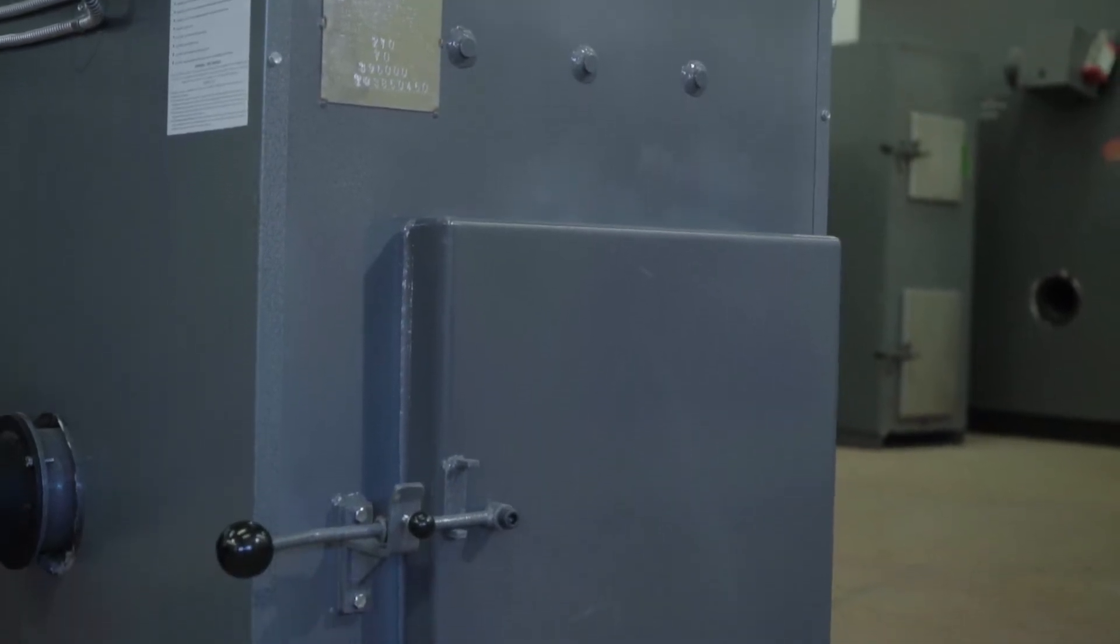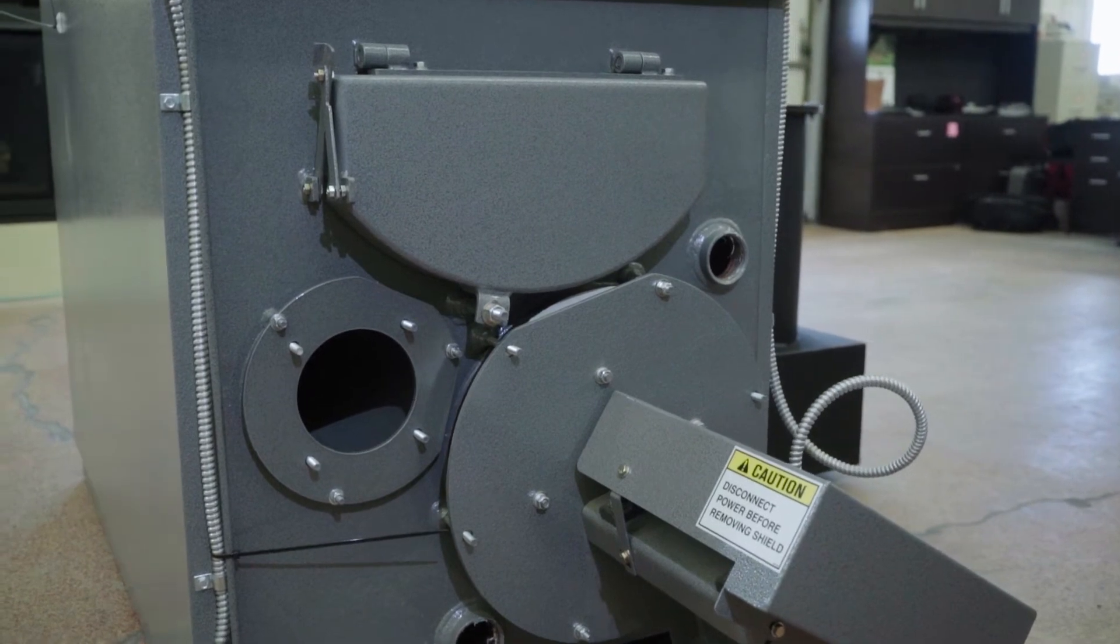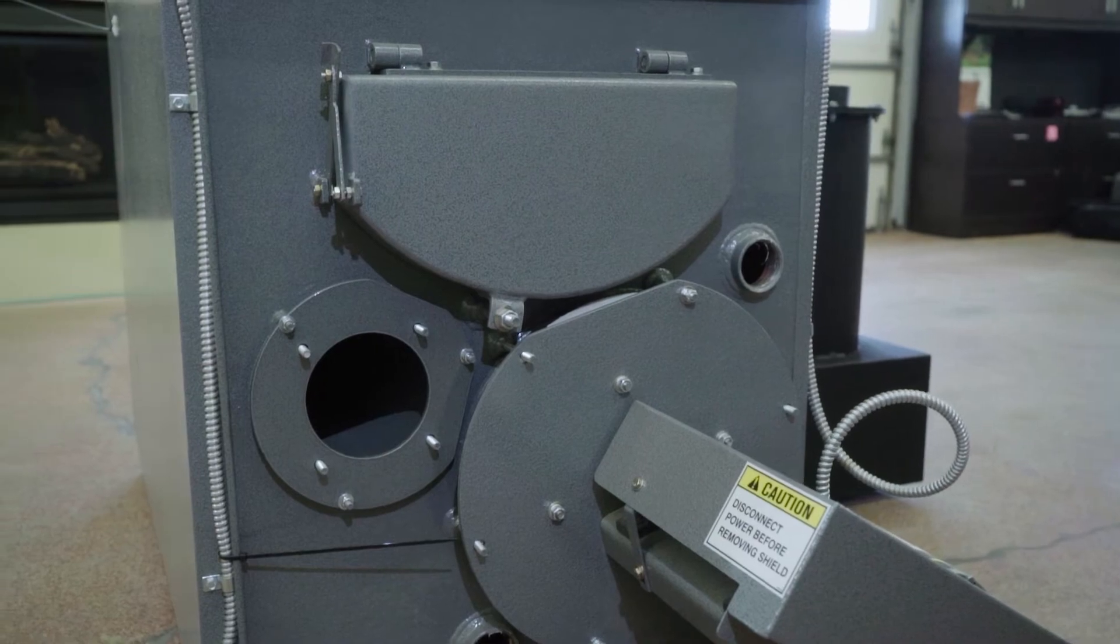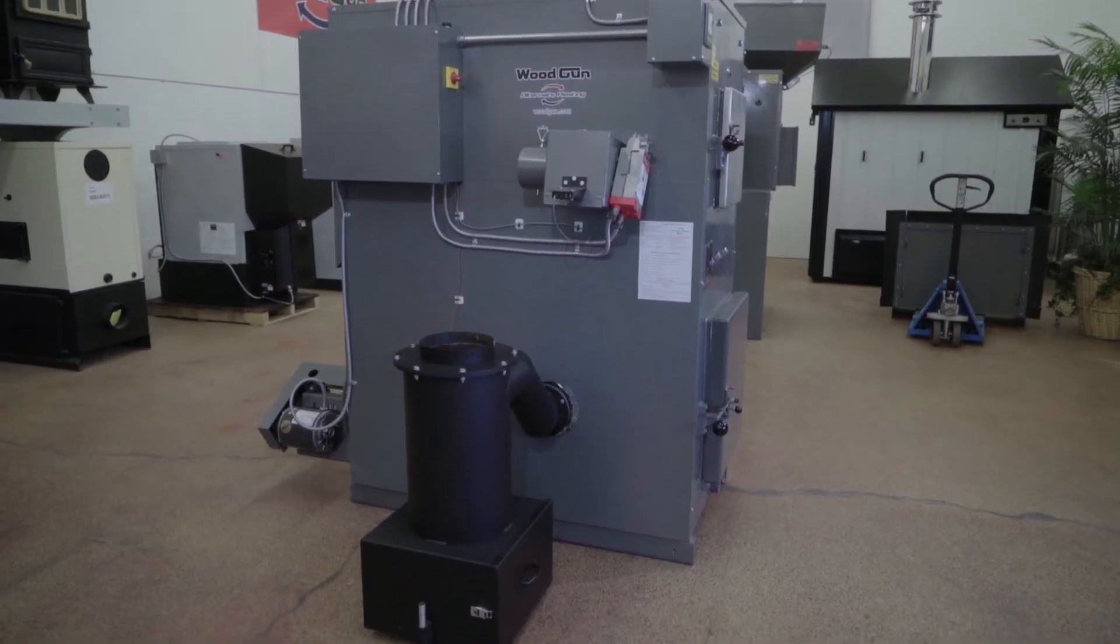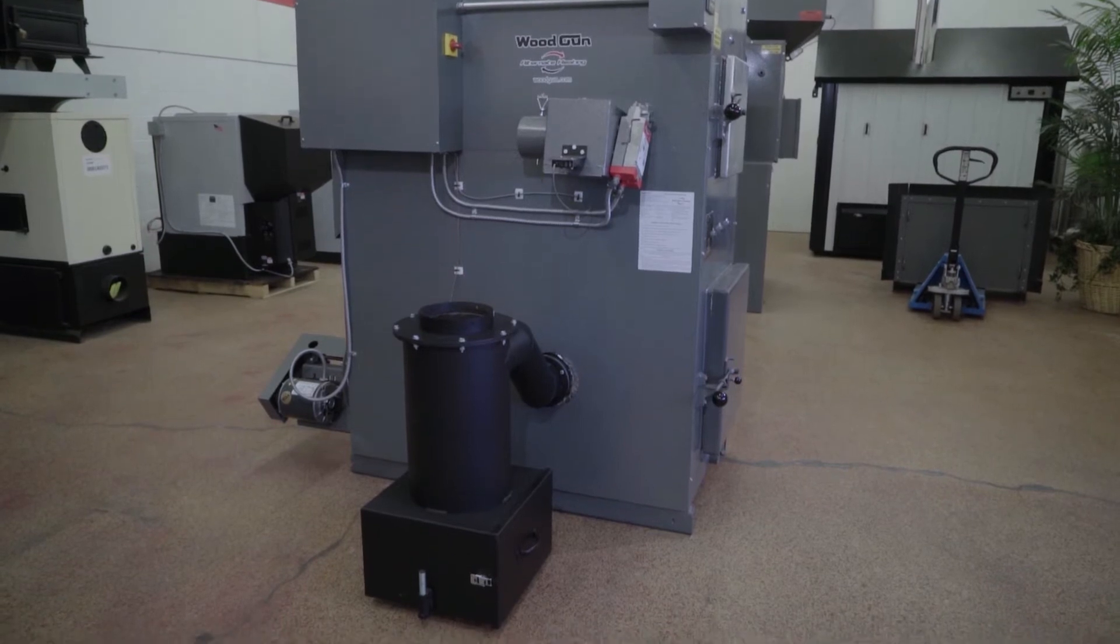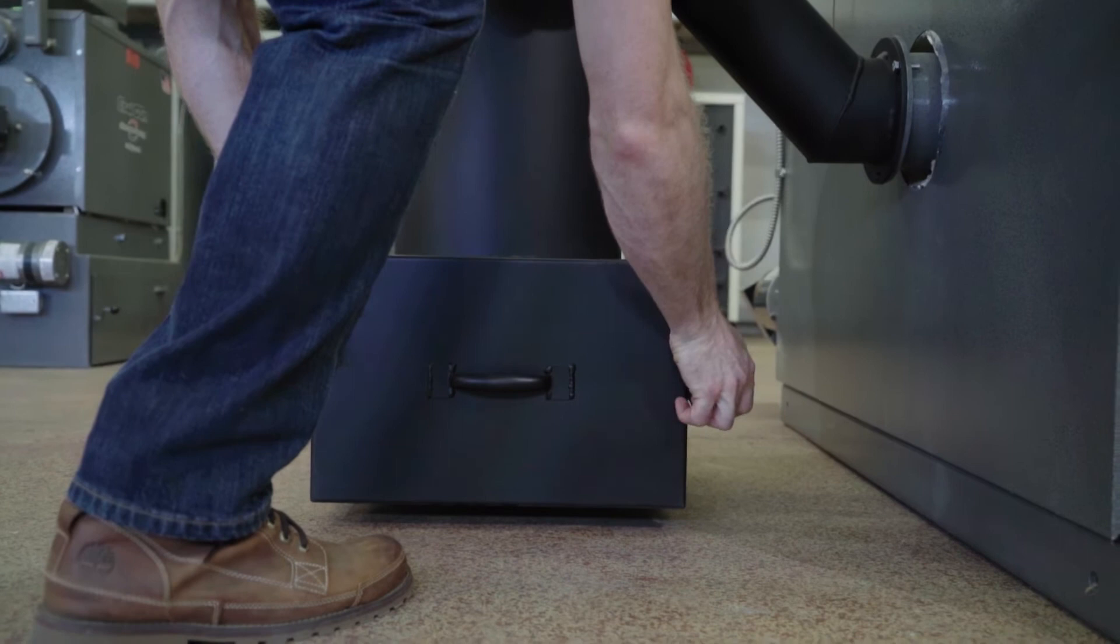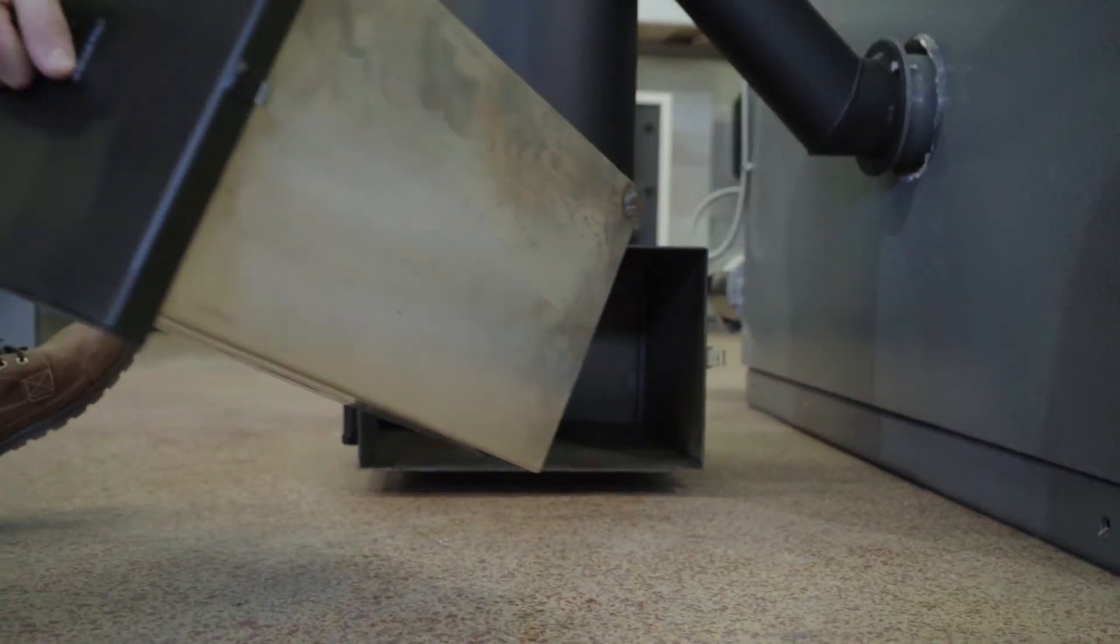There is a yearly maintenance which requires cleaning the heat exchanger, and it's very simple to do. Just remove the fan at the back of the boiler and simply scrape it out. You will also need to remove the cyclone and clean your flue at the cyclone exhaust port. The weekly maintenance is minimal and all it requires is emptying the ash from the ash pan and scraping the center tunnel with the provided ash scraper.